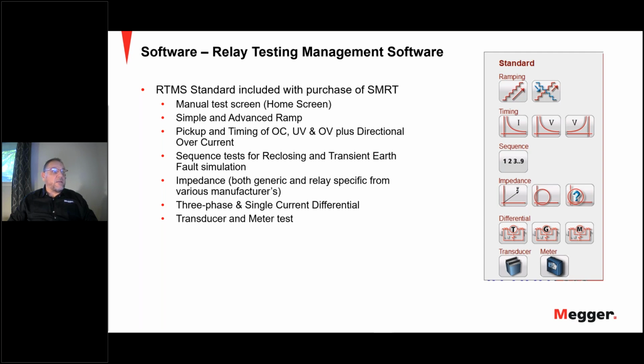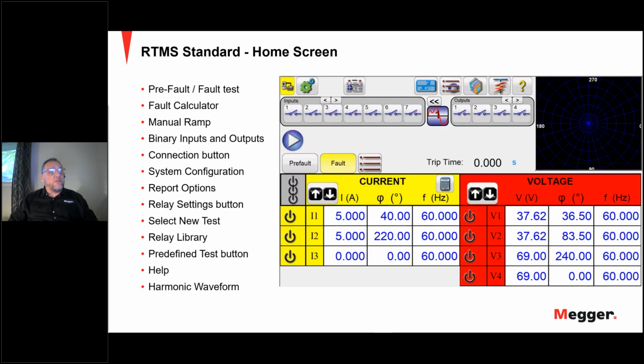The RTMS standard includes the manual test screen or the home screen, simple and advanced ramp, pickup and timing of overcurrent, under voltage, and over voltage, plus directional overcurrent, sequence test for reclosing and transient earth fault simulation, impedance, both generic and relay specific from various manufacturers, three-phase and single-phase current differential, and transducer and meter testing. Now, I'm going to go over these screens a little bit, not in much detail, but just to give you an idea of how powerful the software really is and what can be achieved using this software.